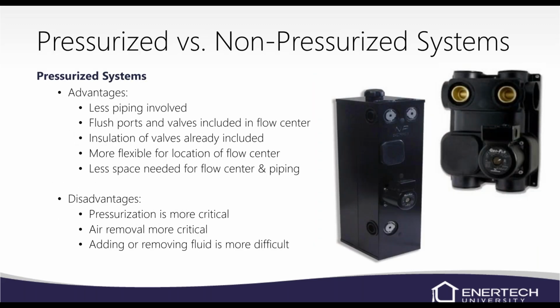Pressurized versus non-pressurized, a lot of times it's just a matter of preference. They both will get the job done. I have a lot more experience with the pressurized, so I prefer pressurized, but there's a lot of guys out there that don't like the pressurized due to maybe air in the system or something, or they're just used to using it. And again, it's preference. It doesn't affect the way the unit is going to operate.